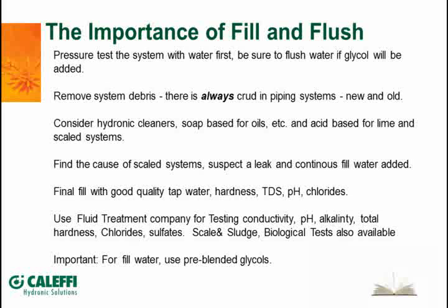You're trying to get the heat energy from the flame into the fluid, so any little insulative layer that you put on there, be it a hard scale buildup or dirt and debris, you want to flush that out of it. And for the very final fill, after you've cleaned out your system and flushed all the dirt and debris out and made sure it's leak tight, you want to use a good quality water. And you'll notice that now most of the boiler manufacturers actually give you a spec on the water. They'll usually tell you what they want the pH to be, the range for that, the hardness.